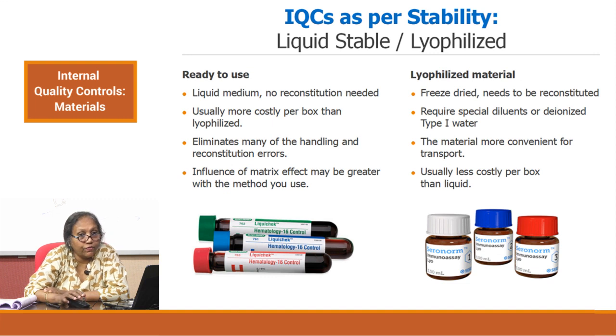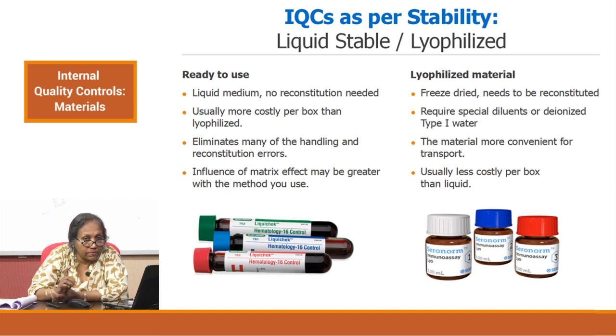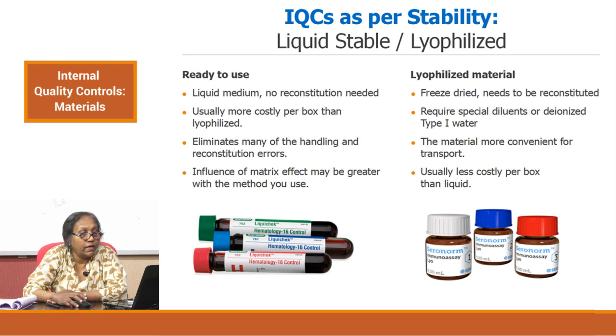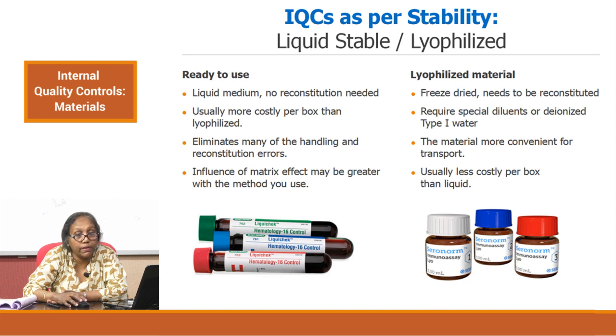There is one more way to classify controls — as per stability — either ready-to-use or lyophilized material. For ready-to-use material, it is generally in liquid medium and no reconstitution is needed. It is usually more costly per box than lyophilized material, but it eliminates many handling and reconstitution errors. However, the influence of matrix effects may be greater with the methods used — that is a negative point where liquid stable controls are concerned.